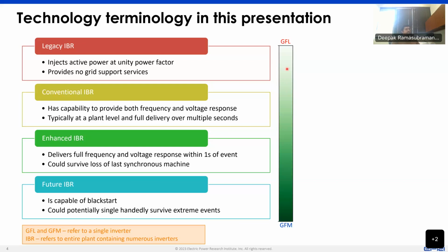So grid following and grid forming are more of bookends. They're more of bookend terminology, where what is known as grid following in a lot of the material out there in the industry is actually towards the legacy IBR spectrum. And what is known as grid forming is potentially more towards the future IBR spectrum. And a lot of times, this terminology of grid following and grid forming refers to a single inverter. But an IBR resource, an inverter-based resource, is usually an entire plant that contains numerous inverters.